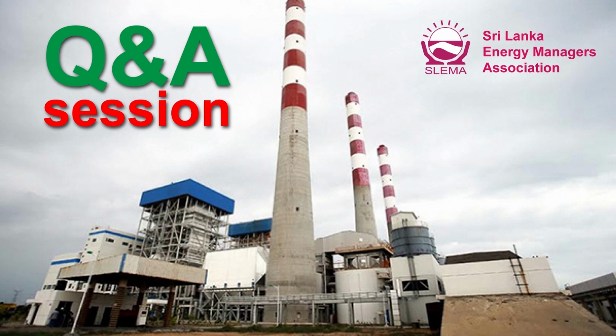Of course, the normal hot startup has to be carried out. It still takes some time because you have to start from zero. So it takes time to start the power plant, even if you manage to recover from the trip. You can't get 300 megawatts right away. You have to start low, maybe from 15 megawatts. You reconnect it and then slowly keep on adding coal to the boiler and reach the required temperatures. And then finally you can achieve 300 megawatts.